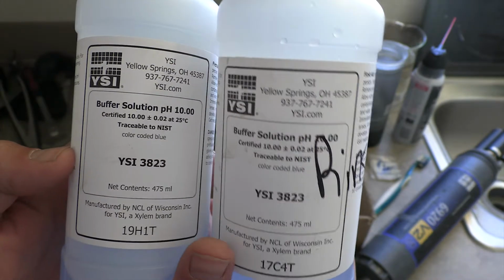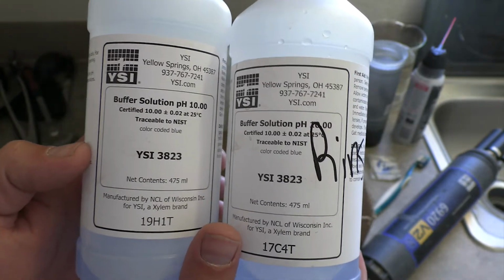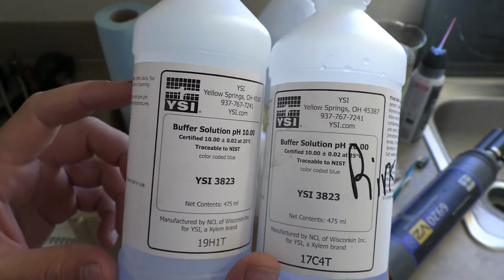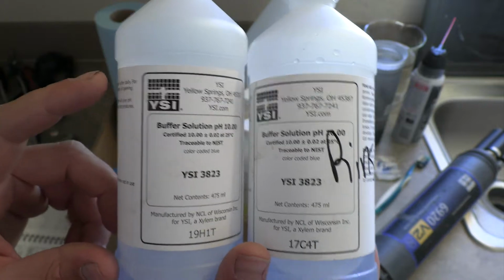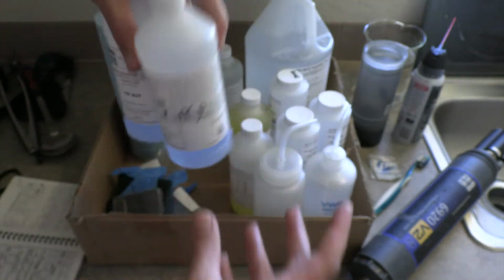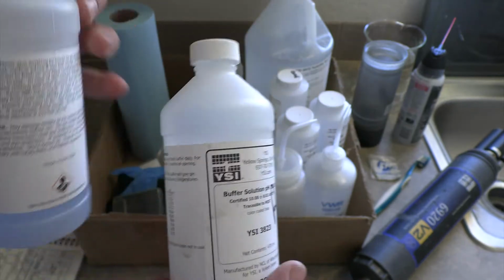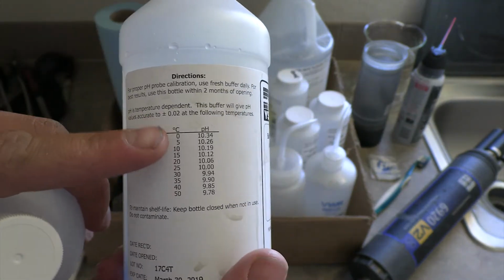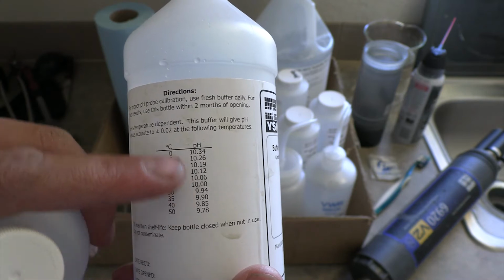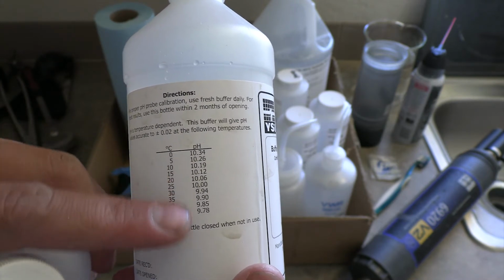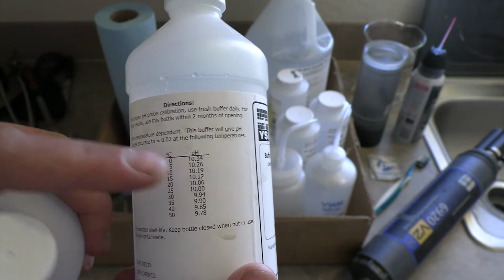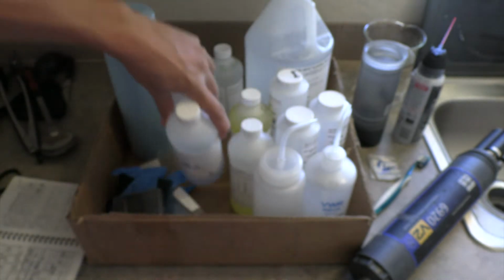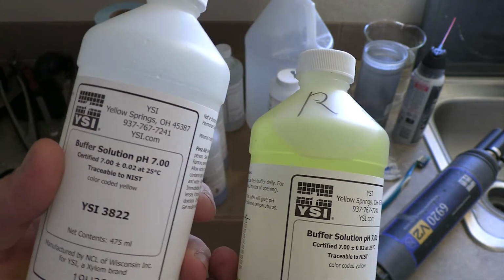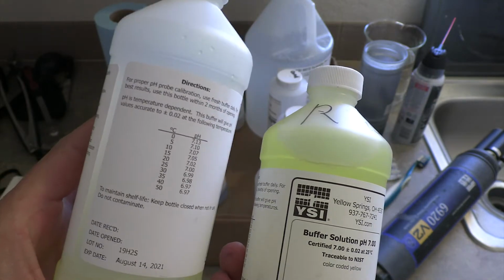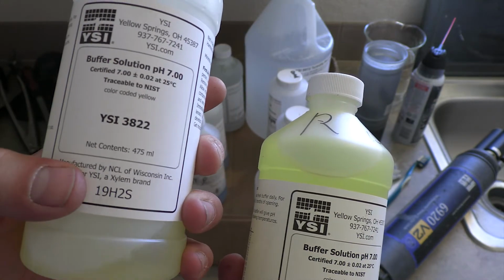For pH, there are different volumes you need to put in each, and the deepest, the one that you have to put the most solution in for, is the conductivity. That needs to be over the top of each, but we'll go over that in a sec. The other thing you have to remember about pH is that it's temperature dependent. So if the temperature is different, the actual pH is going to be different. So you wouldn't calibrate it to 10, you'd calibrate it to 10.06 or 10.12. You just have to keep that in mind for pH. And then this is our pH 7 here, YSI 3822. Same thing, it's temperature calibrated, and the lot number is right down there.